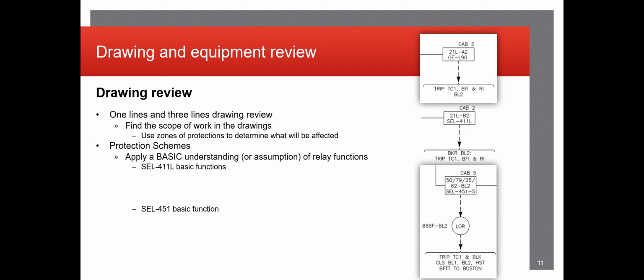So we're going to be going over the drawing equipment, the 1 lines and 3 lines drawing review, finding out what zones of protection will be utilized and what relays will be associated with them, and apply a basic understanding of the relay functions for, specifically in this case, the 411L and the 451. The 411L is commonly a line protective relay. It's a single-ended protection that can communicate based on tripping, and also offers reclose initiate and breaker failure initiate, which is what the RI and BFI stand for.